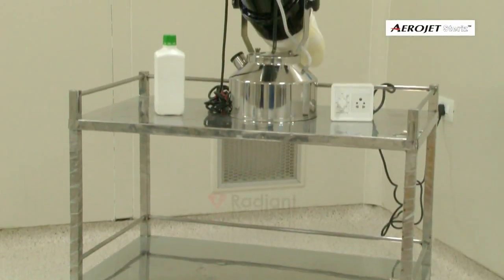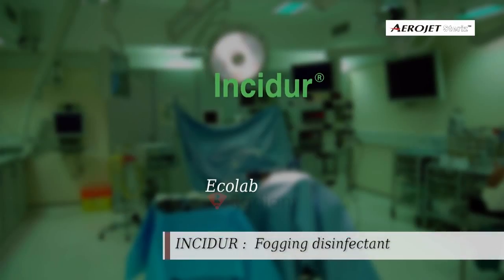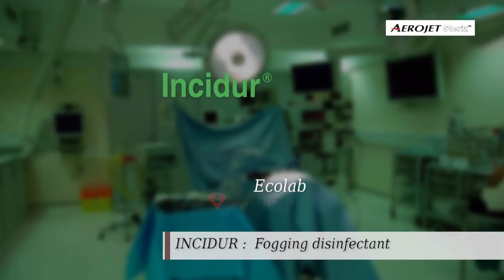which clearly mentions preparation of disinfectant solution and duration of fogging treatment. Place the fogging system on a steady surface at three feet height such that there are no chances of it falling down, even while in running condition. Incidur from Ecolab is the recommended disinfectant.